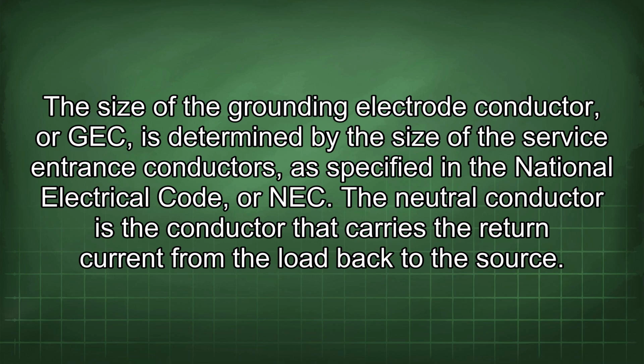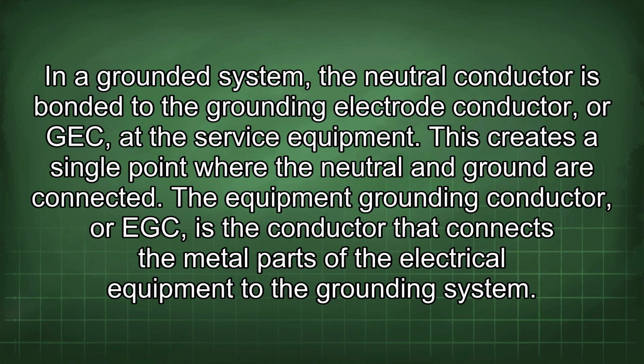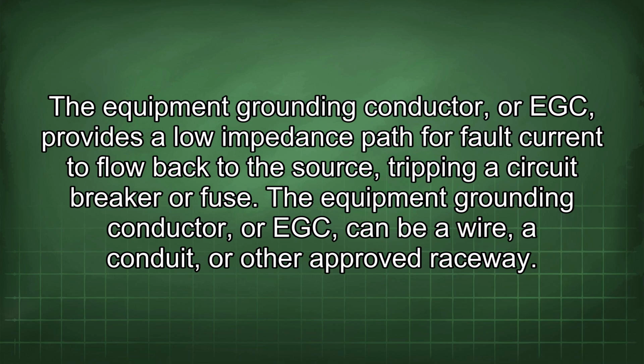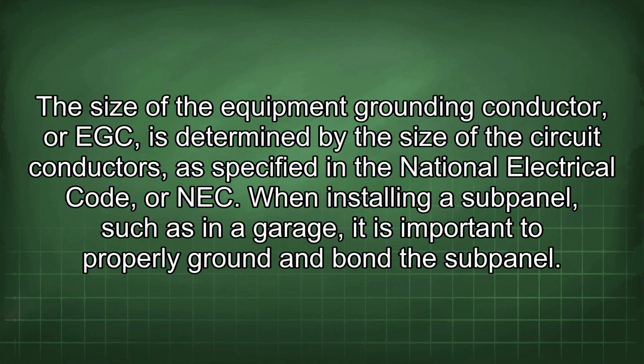The neutral conductor is the conductor that carries the return current from the load back to the source. In a grounded system, the neutral conductor is bonded to the grounding electrode conductor, or GEC, at the service equipment. This creates a single point where the neutral and ground are connected. The equipment grounding conductor, or EGC, is the conductor that connects the metal parts of the electrical equipment to the grounding system. The EGC provides a low impedance path for fault current to flow back to the source, tripping a circuit breaker or fuse. The EGC can be a wire, a conduit, or other approved raceway. The size of the EGC is determined by the size of the circuit conductors, as specified in the National Electrical Code, or NEC.